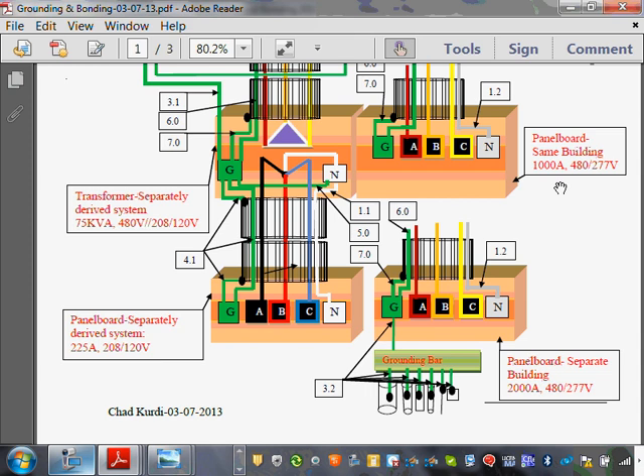Now, if you guys do solar photovoltaic systems? Nobody? The only thing that's not covered here is bonding for DC systems, solar photovoltaic systems. Typically, they take the grounded conductor, they ground the negative, and they ground it through a fuse. So you take the negative to one side of the fuse, out of the fuse, tie it to the ground. So for a negatively grounded solar photovoltaic system, that's how they do it. They size the conductor based on the size of the hot conductors coming to the combiner box. So if your positive conductor is one size for that system, your grounding electrode conductor would be the same size. It's not here. Any comments, guys?